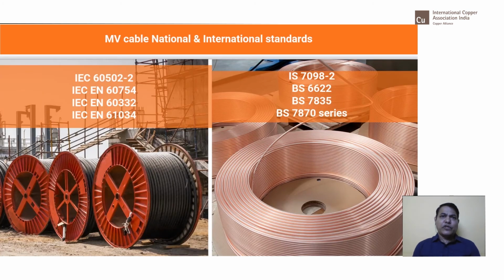With the increased use of alternative materials, it is also an easy way for a cable manufacturer to differentiate their product ranges, adapting to cheaper material to build up the cable. I mean, to reduce the cable cost. So that is the reason a type test should be repeated once it is done, and it doesn't give a guarantee of consistency if it is not tested in between by a third party. As a result, it also calls for independent type testing before the product reaches the market. In medium voltage cable, normally the concept and requirement is that a type test by a third party is very important. And the approval body believes any changes made to the cable design or even the process have to be retested or re-type tested.